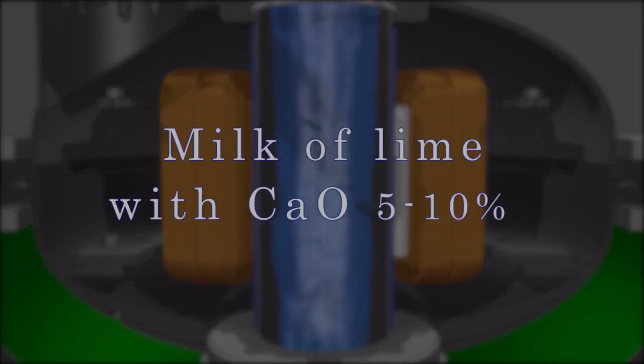The research into decontamination of wastewater in the AVS has shown that the magnetic mill is more efficient compared to equipment currently used for this purpose. Converting phosphates into water-insoluble compounds occurs in one stage. The duration of treatment is 1 to 3 seconds. The reaction uses lime with 5 to 10% excess calcium oxide of the theoretically required amount.